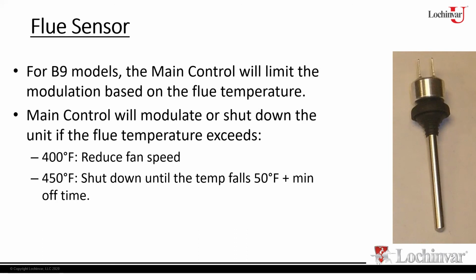Now, for the M9 models, for your F9 models, basically it really serves no purpose. However, there is a limit to it. So I guess that would be your only purpose, to ensure that it doesn't get too hot. So in this case, if it sees that the stack temperature exceeds 400 degrees, that's going to limit the firing rate. If it continues to rise and hits 450 degrees, it will shut the heater off.